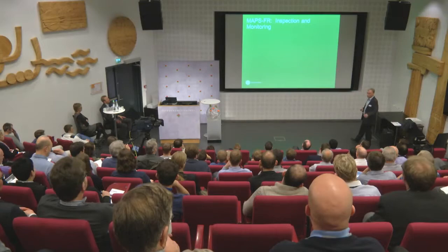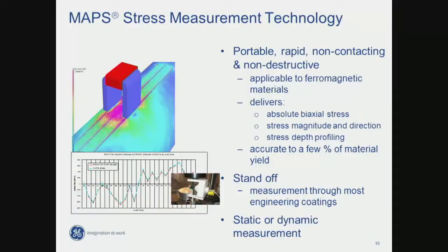I've got one slide on what the technology does, then I'll flip straight into what we're doing for flexible pipe. So what we do is measure stress. The M is magnetic, it's a magnetic technique, we measure stress on ferromagnetic materials, so a magnet needs to stick to it. It's an absolute measure, and we deliver megapascals from that absolute measure.